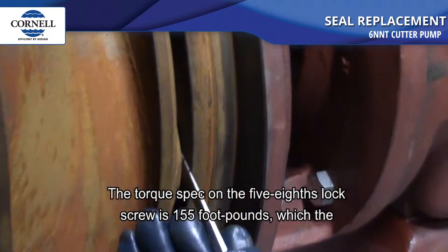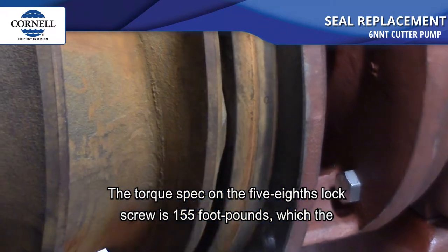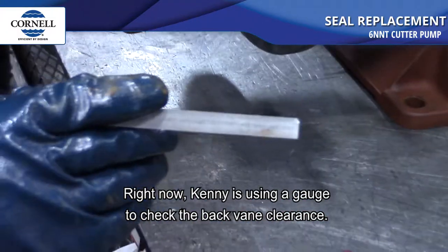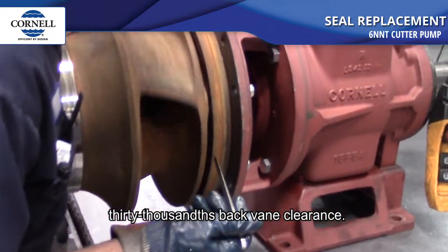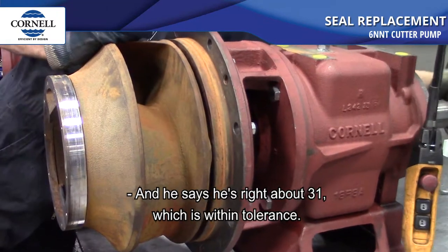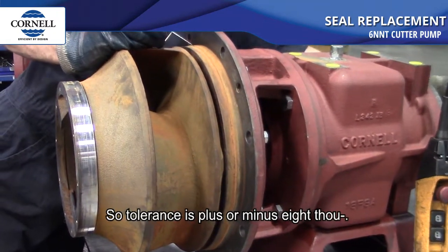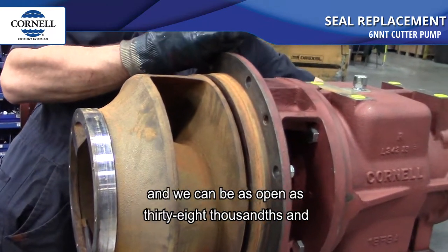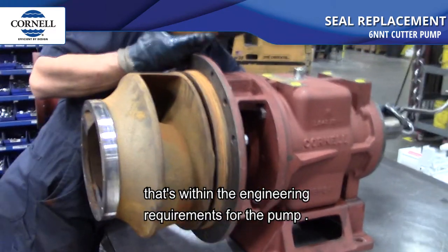The torque spec on the 5/8 lock screw is 155 foot-pounds — the air guns get it right around 155 to 160, somewhere right around there. Kenny's using a gauge to check the back vane clearance, going around all the vanes checking for 30 thousandths. He's right about 31, which is within tolerance. The tolerance is plus or minus 8 thousandths, so anywhere from 22 to 38 thousandths meets the engineering requirements.